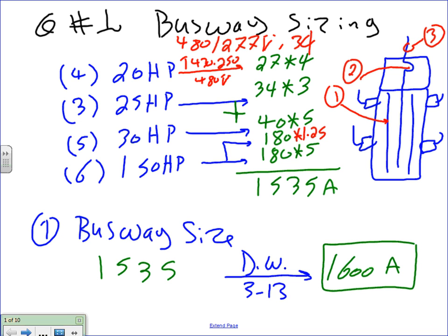Yes, sir. You first from us, yeah. What I did a lot ago, I split this six into two parts. One is one of them and five. Six, I split them into groups of one and a group of five. The five multiplied by 180, and the one, I assume it's the largest, fattest, fluffiest motor, and I added 25% on it. In the bigger scheme of things, guys, 25% on the largest motor on a system like this is worthless. If you do the calculation without the 25%, it wouldn't make a difference, because the system is so big. 25% on one motor doesn't make a big difference here. But we still do it.